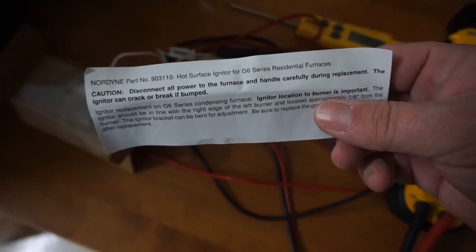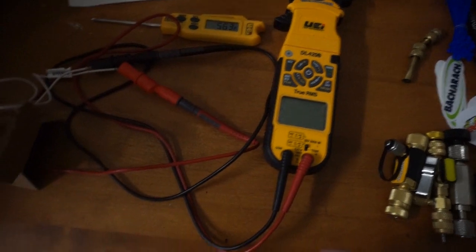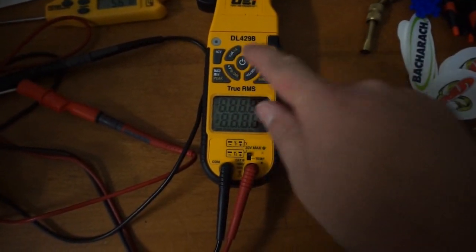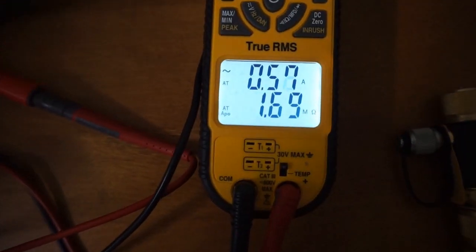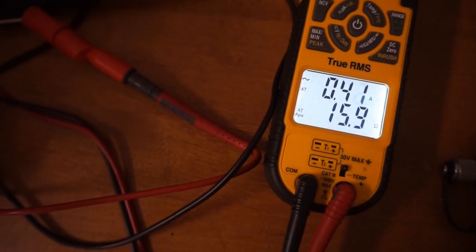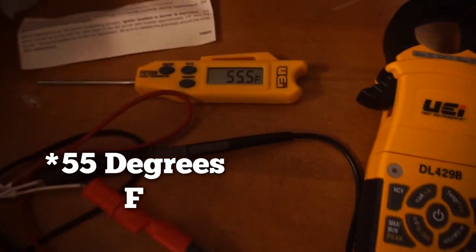I now have a different igniter here, still inside the wrapper because I don't want to damage it. This is a hot surface igniter for a G6 series residential Nordyne furnace. I've had this thing for a long time, it's just been sitting here, so I wanted to check it out too and we're almost the same temperature — 56.1 degrees. Turning on the DL429, let's see how many ohms we are. It looks like we are 16 ohms, so quite a significant difference from igniter to igniter. Not going into specifics of which igniter is which type, just kind of getting a feel for how the variation might be.